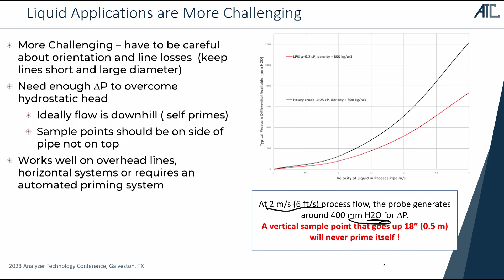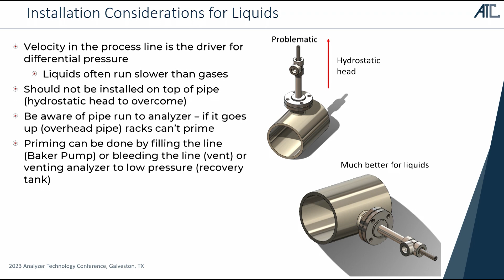So when we do the installations for liquids, our ideal installation is to sample off the side of the pipe and ideally have the analyzer be lower down, or the composite sampler, the grab sampler, whatever it is. Otherwise, we're going to have to consider how we are going to get that to prime. Once it starts to flow, it's a siphon and it just keeps on going. But we may have to add a mechanism for priming if we're going to run uphill.